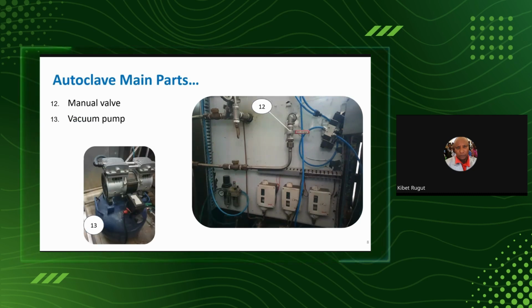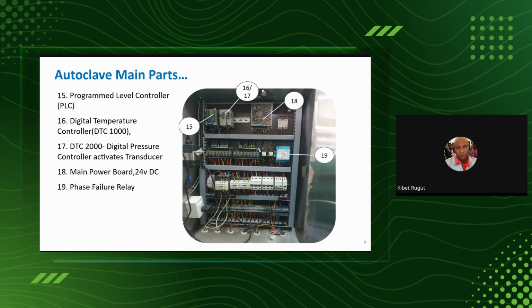Then we realize that we have a vacuum cycle or a pre-vacuum, and you need a vacuum pump that is very robust. And also, if you need the pneumatic valves for closing and opening some of the switches, you also need a compressor. So here again, inside here, you can have manual bypass valves that may be operated semi-automatically, or in emergency moments, you may be asked to switch off a certain valve manually. But again, you can see the pressure valves are also there, and they can be set to the range that the manufacturer recommends.